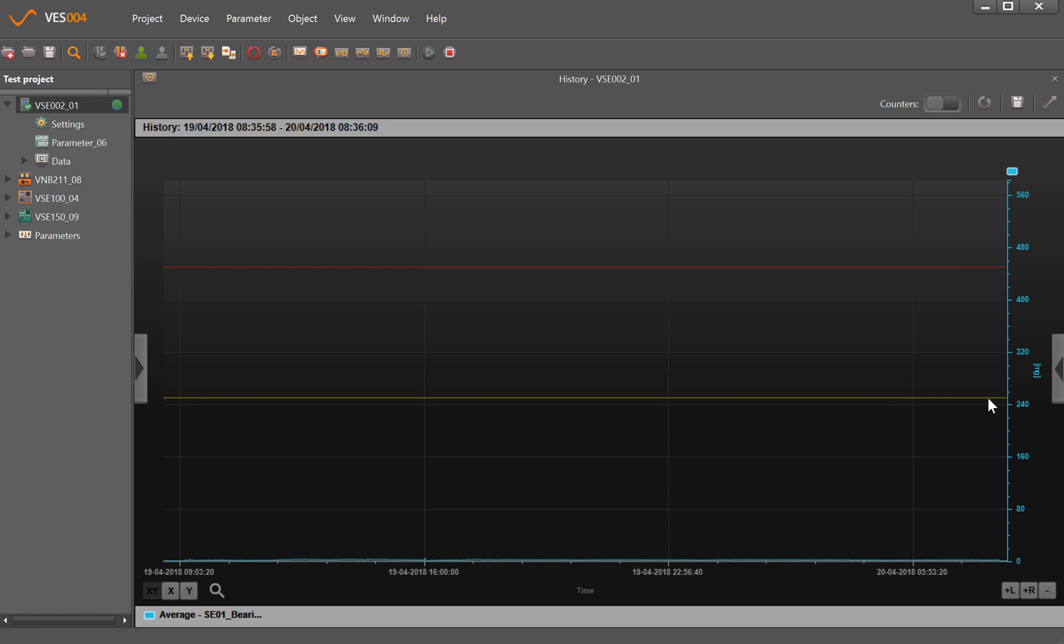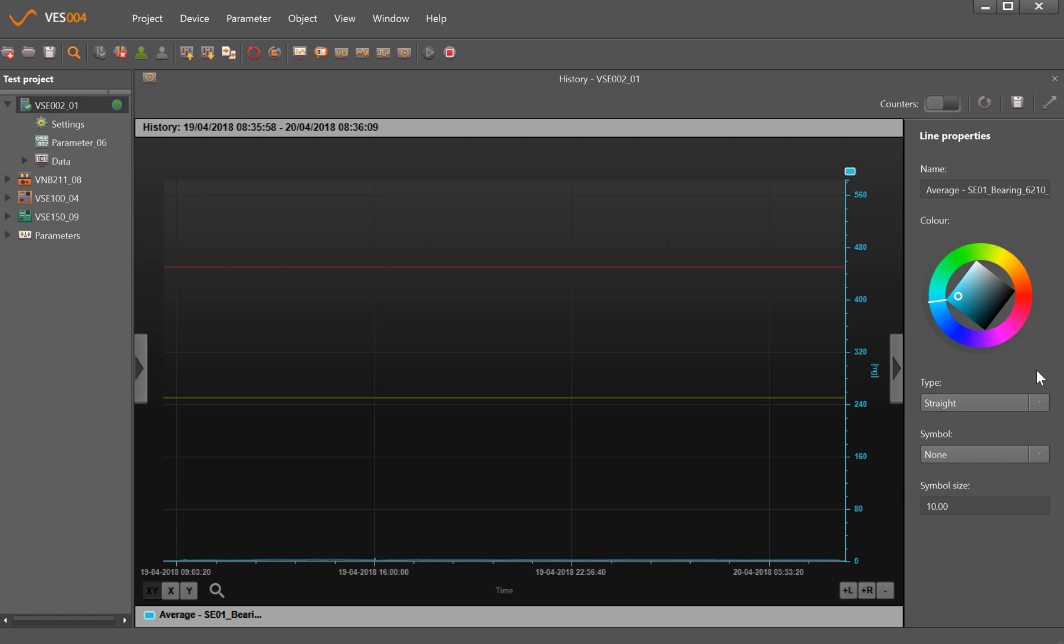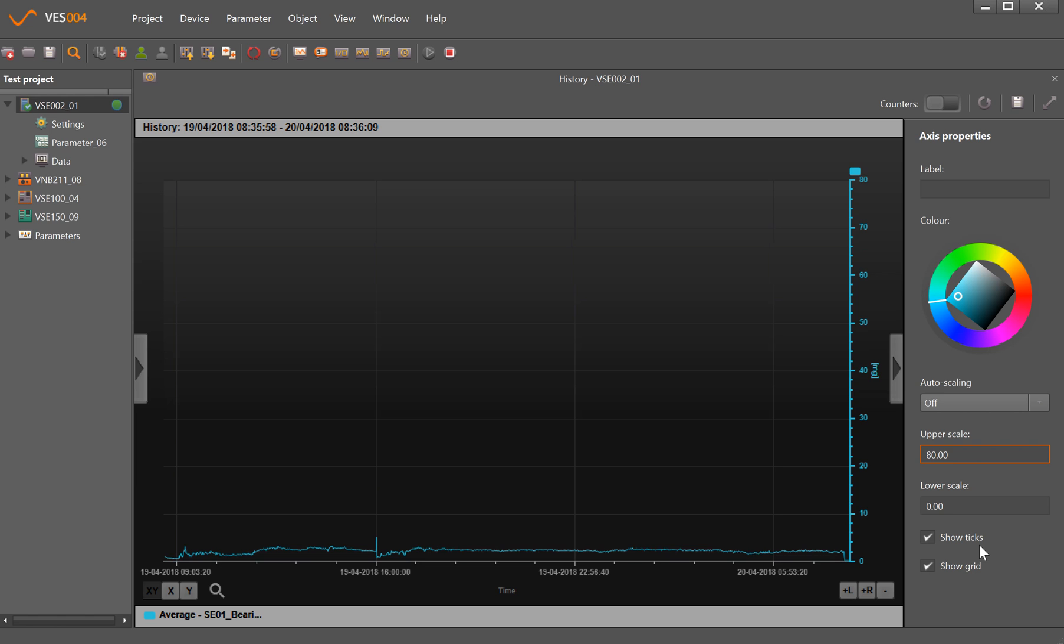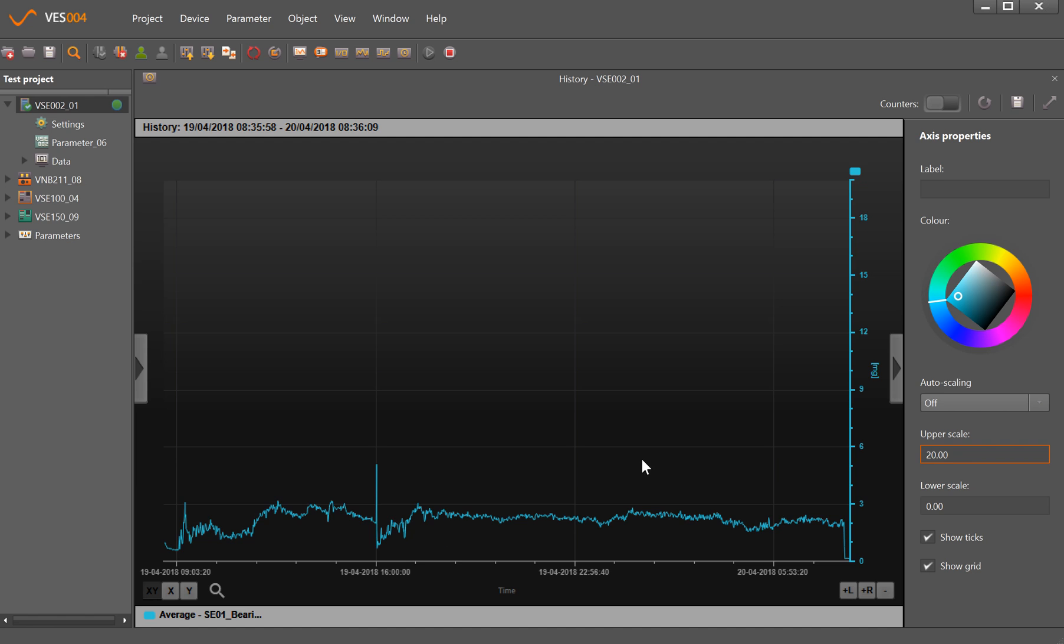Not sure if you can make it out, but down the bottom here we actually have the history trend, but it's so low. So if I want to change the scaling, I can click on the tab to the right here. And if I then just where this y-axis is, if I just click on it with the mouse, it makes it a little bit brighter so we've now highlighted that. I then have the option here where it says auto scaling, so I click auto scaling to off and then change the upper scale to say 80. That will now zoom in and show me the trend. I'll maybe just go in once more, maybe set that to 20.